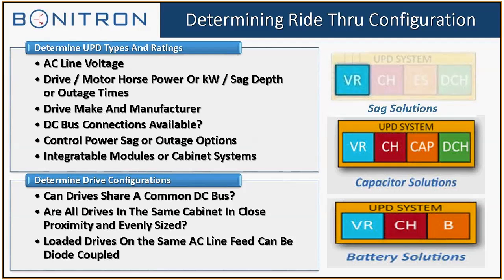Then also, if you don't back up the control power, there's no sense in backing up the drive. You can back up the drive all day long, but if the control power is wiped out, it's going to wipe out the whole process too. So we want to find out, usually the customer deals with the drive and the control power separately. Control power can be PLC networks, relays, light curtains, things like that. So we need to know how the control power is being handled, and usually we can provide an option for that.